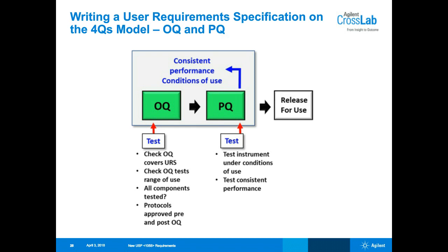You will carry out checks using calibrated equipment, reference standards, calibrated masses, etc., and you want to make certain that all the components are checked and also a holistic check of the whole instrument, including the software. Make certain that protocols are approved pre-execution and also post-execution, because you are responsible for the work of the service engineer carrying out this qualification work in your laboratories.